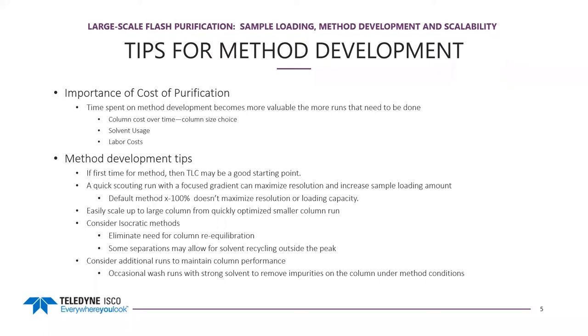It's easy to scale up to the large column from a quickly optimized smaller column run. If you're doing multiple iterations of purification over time with multiple injections, consider using isocratic methods — this could eliminate the need for column equilibration. If you've got a really pure starting material with two closely eluting compounds, isocratic methods can separate those and minimize column equilibration needs, and potentially enable solvent recycling outside the peak. When doing method development with multiple runs over time, consider wash runs at the end or after so many runs to restore the column by removing impurities that bound under the optimized method conditions.